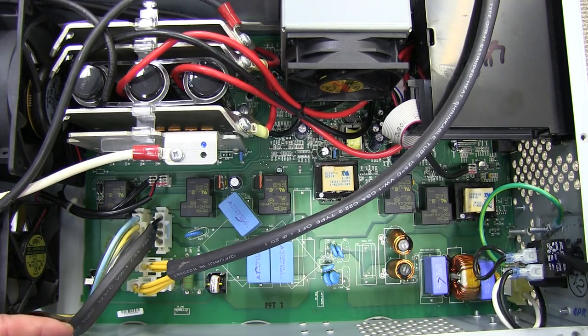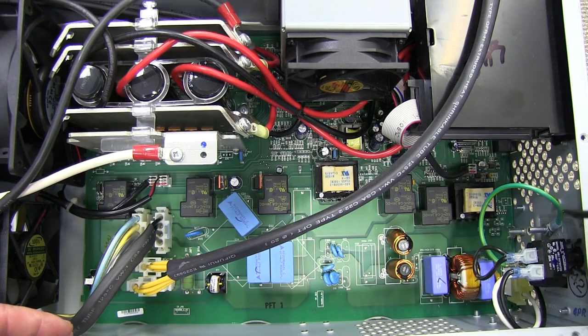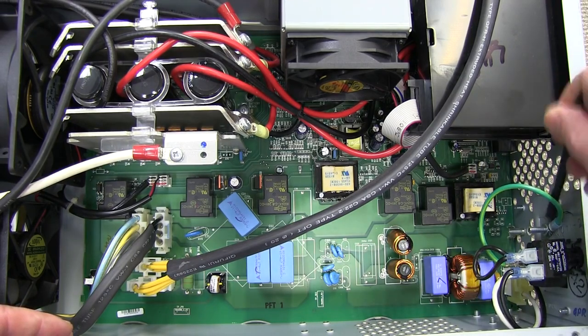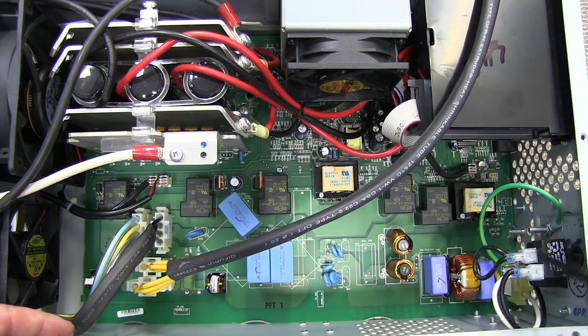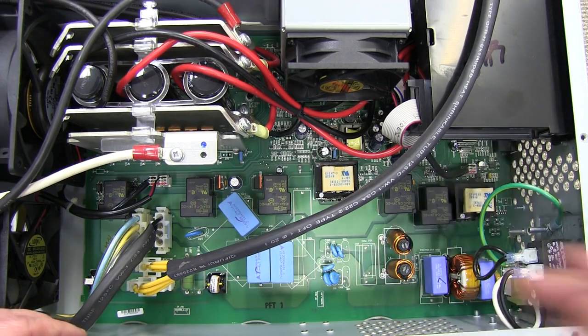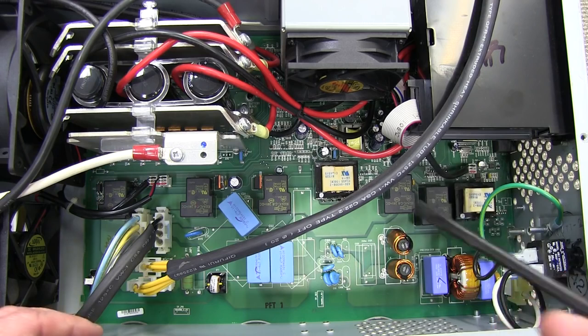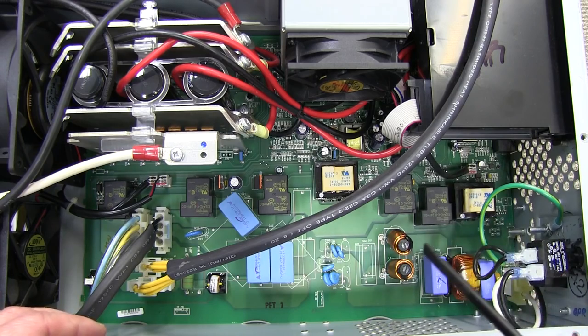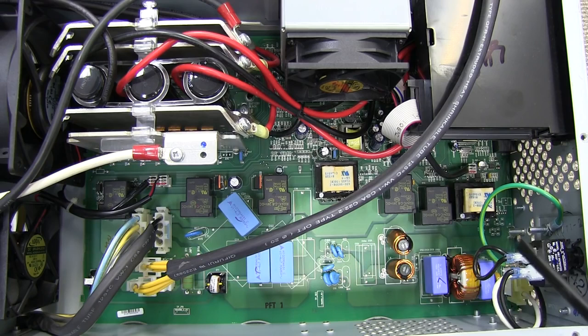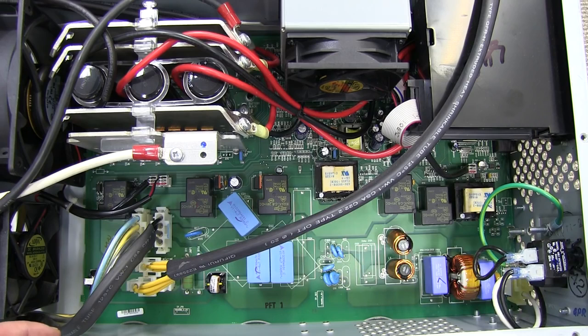So we've got our mains input over here, securely clamped down to the chassis with earth. And remember, as I said, because this is a line interactive UPS, it is not isolated. So the transformer is an auto transformer, so the mains output is not isolated from the mains input.